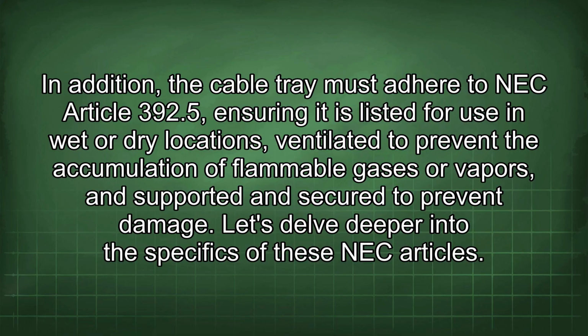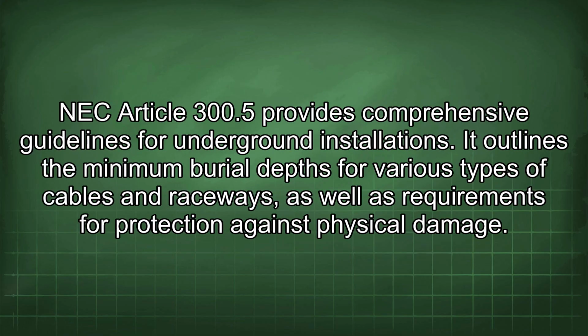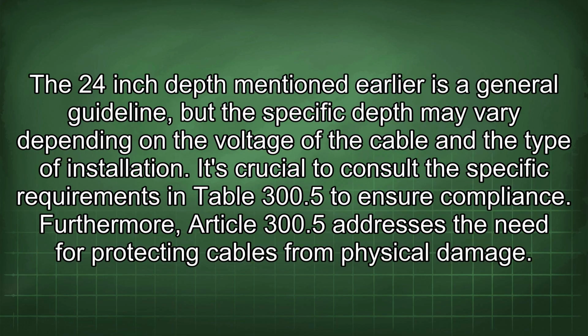Let's delve deeper into the specifics of these NEC articles. NEC Article 300.5 provides comprehensive guidelines for underground installations. It outlines the minimum burial depths for various types of cables and raceways, as well as requirements for protection against physical damage. The 24-inch depth mentioned earlier is a general guideline, but the specific depth may vary depending on the voltage of the cable and the type of installation. It's crucial to consult the specific requirements in Table 300.5 to ensure compliance.